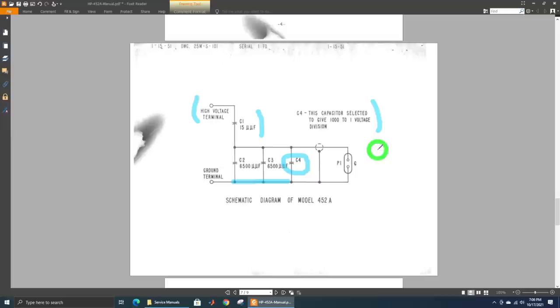The grounding of this is really important, because if you don't ground that, the entire thing can shift up in potential and can be quite dangerous. There's also this component here. This could be protection against very high voltages, but that's not the spark gap because the spark gap would have to be here so that the voltage is between it and the high voltage input. This should be grounded here so the voltages between these two nodes cannot exceed 25,000 volts RMS, otherwise an arc will form.